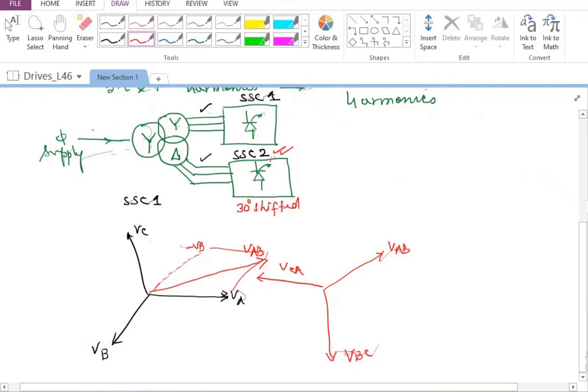So if I look at the harmonic content here, we are going to see that fifth and seventh harmonics are going to be exactly cancelling out each other from this converter and this converter. So we will be devoid of fifth and seventh harmonic. So the lowest order harmonic in this particular case is going to be only 11th and 13th. So we will not have anything less than 11th or 13th order harmonic in this particular case.